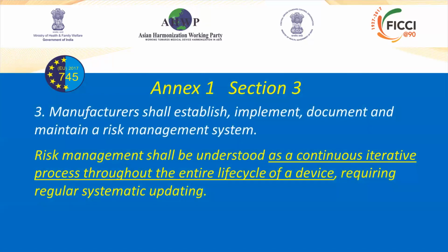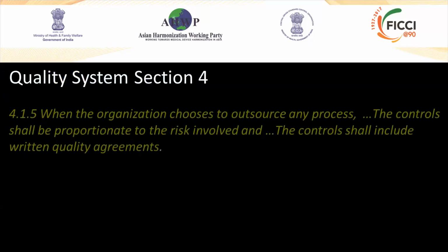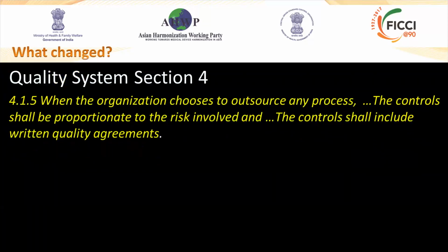This remains true in the new medical device regulation in Europe, and you'll see this in Annex 1 of Section 3, where there's a much greater focus on risk management. It says it shall be understood as a continuous iterative process throughout the entire life cycle of the device. So there's risk management you will be seeing popping up in post-market surveillance and that sort of thing. So that's risk management really through the life cycle of the medical device.